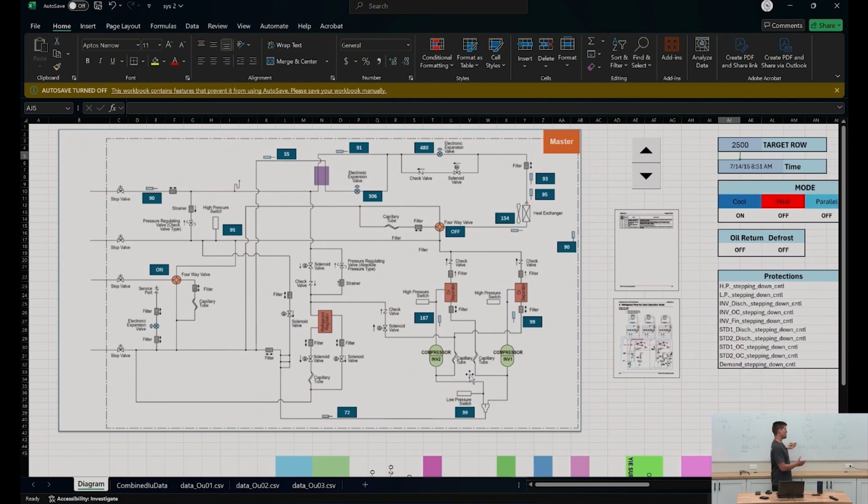You can look at it in Service Checker, and you can say, "Hey, I really don't know what's going on, but I know this is really bad right here." So then I can go back and I can say, "What's the timestamp in the bottom right of Service Checker?" Let's say it's 9:20 a.m. Okay. Well, I know here this timestamp is 8:51 a.m. So I could keep going until I get to the 9:20, like I saw in the Service Checker data where things got really bad.